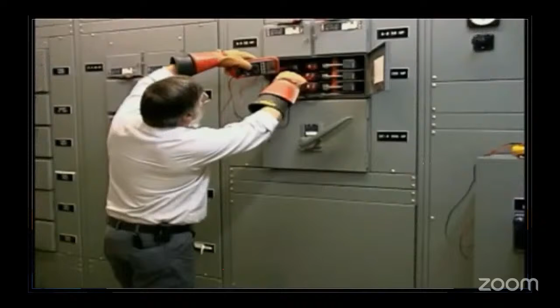The arcs follow the vaporized test probes. If these two arcs join through close proximity of the test probes, one large arc is formed, providing a low impedance path directly from one electrical phase to another. This will cause either a phase-to-phase or phase-to-earth fault. The result is an arc blast, which can lead to a plasma fireball fueled by the energy in the system. When this occurs, temperatures can reach about 6,000 degrees Celsius.